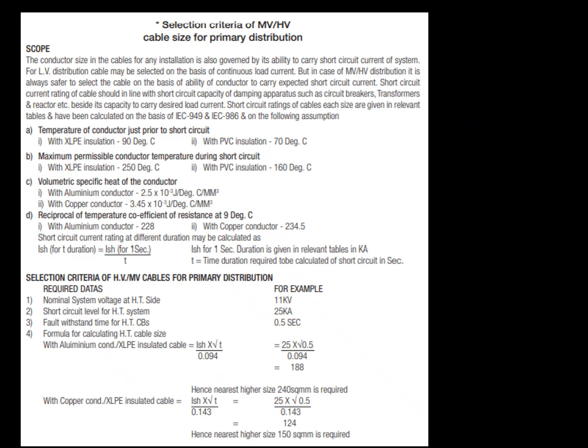Now we'll see the reciprocal of temperature coefficient of resistance at 20 degrees Celsius. With aluminum, it is 228. With copper, it is 234.5. Short circuit rating of different durations may be calculated as per the formula. Selection criteria of high voltage, medium voltage cable for primary distribution. Required data.